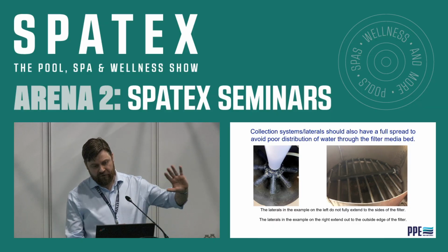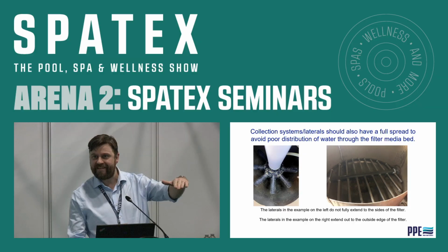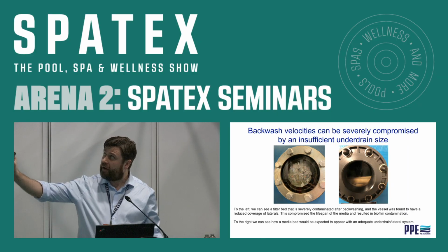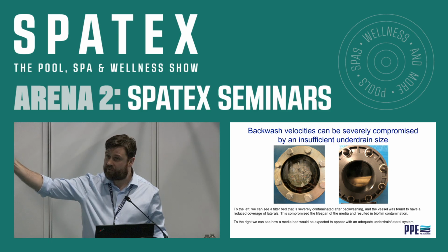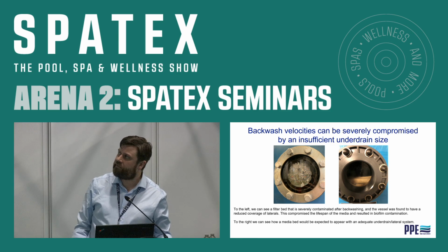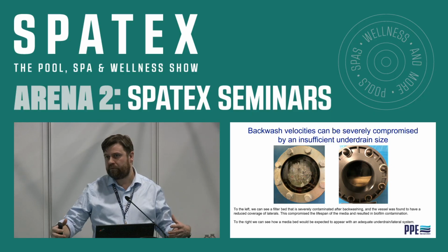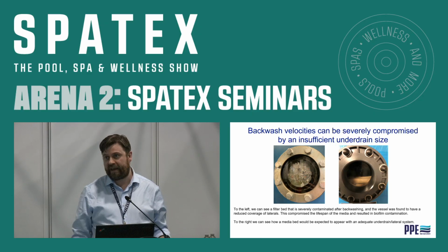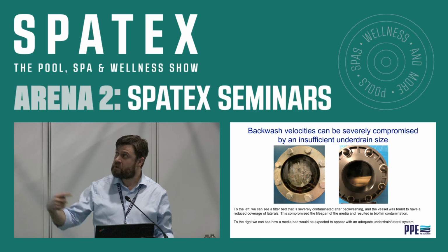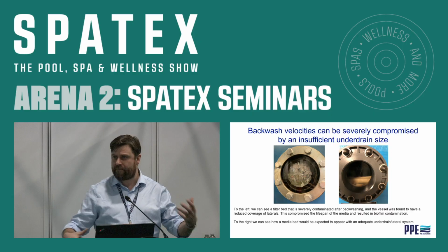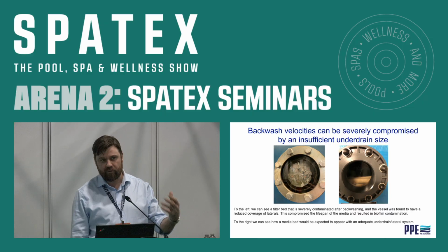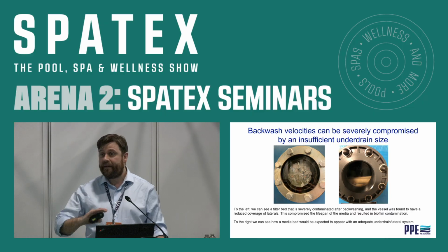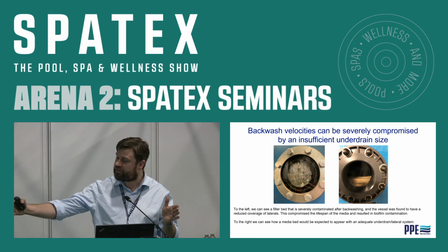Now, if you're fortunate enough and you actually have windows where you can see into the filter, viewing windows, what we should have is what we've got here on the right, after backwashing. If we got something more like here on the left, even following a backwash, then that is showing that there's not much movement at all in particular areas of the filter. We're not able to get a very good backwash. Initially, you might start backwashing a brand new media bed and it might be able to get a bit of movement, it might all be able to lift, but after it starts clogging up with more and more pollution and grease from the bathers, eventually it's going to solidify and it will again be from the outside edges working its way in.